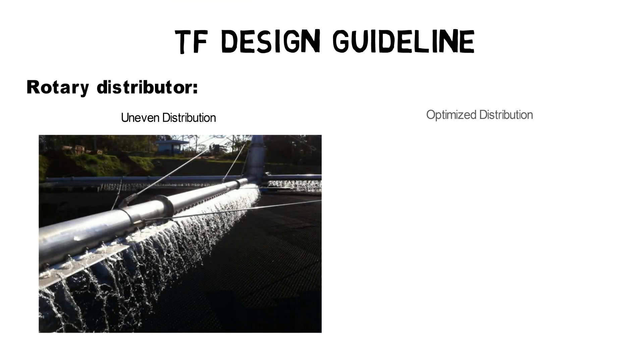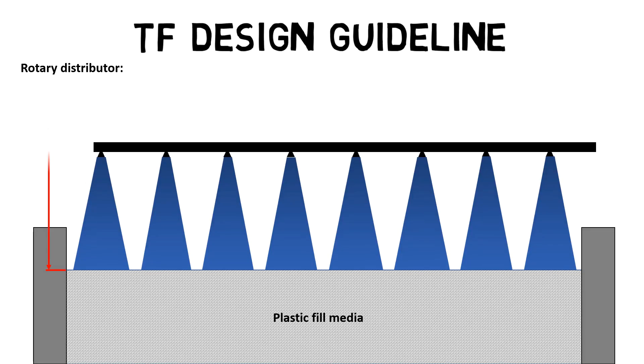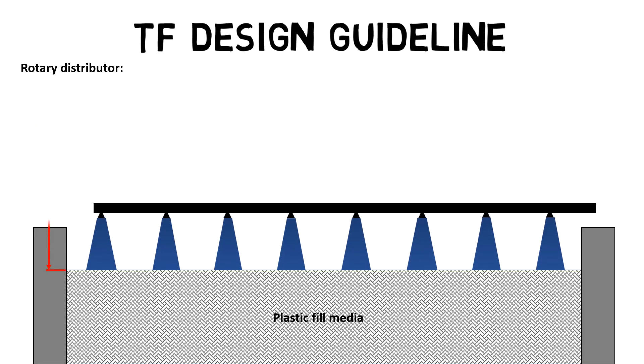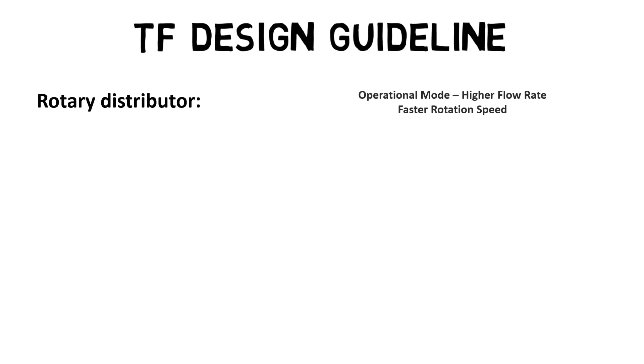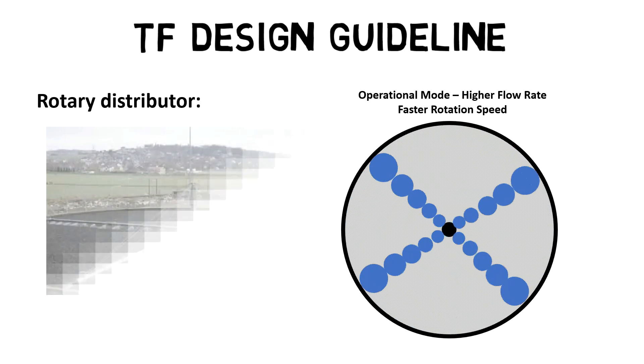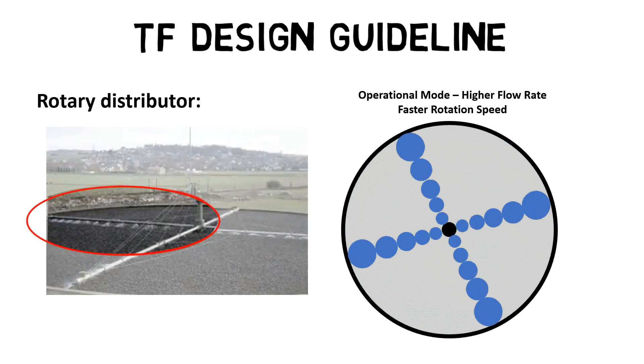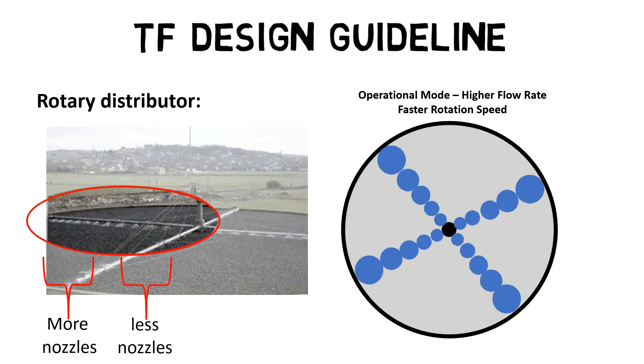The purpose of a rotary distributor is, of course, good water distribution, and it is also used for plastic-fill media flushing. For an even spray pattern, a certain distance between the top of the plastic-fill media and the rotary arms must be determined. As the spray area enlarges with increasing distance from the central shaft, more spray nozzles have to be placed at the end of the rotary arms compared to the beginning.